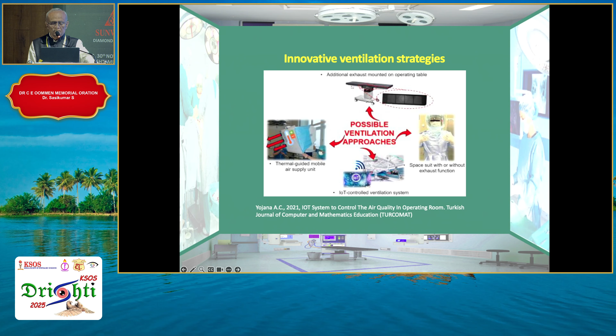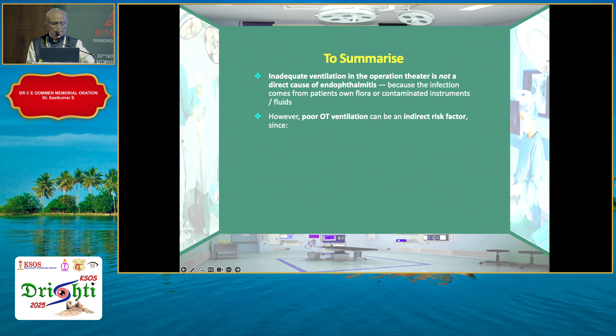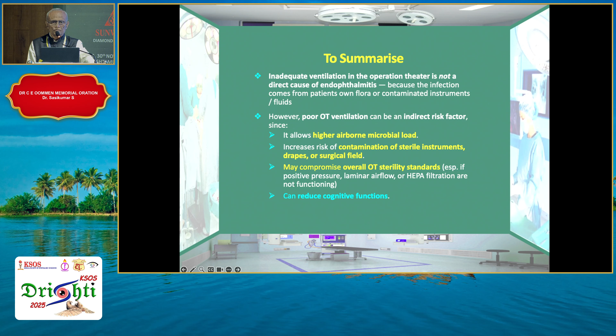So to summarize, inadequate ventilation in the operation theater is not a direct cause of endophthalmitis because the infection comes from the patient's own flora or contaminated instruments or fluids. However, poor OT ventilation can be an indirect risk factor since it allows higher airborne microbial load. It increases the risk of contamination of sterile instruments, drapes, or surgical field. It may compromise overall OT sterility standards, especially if positive pressure, laminar flow or HEPA filtration are not functioning. And it can reduce the cognitive functions, which most hospitals are not giving importance.